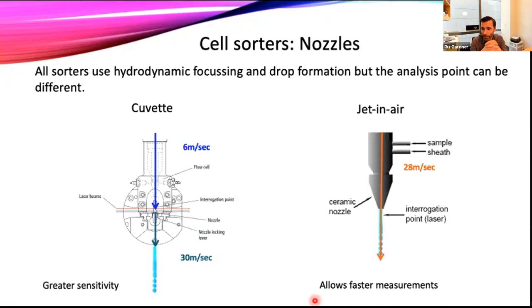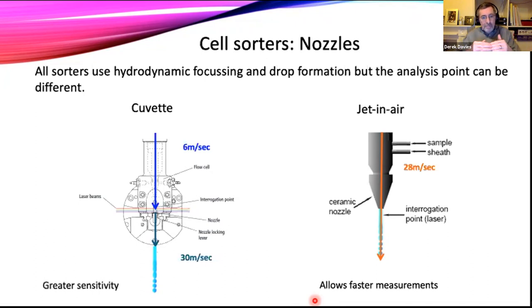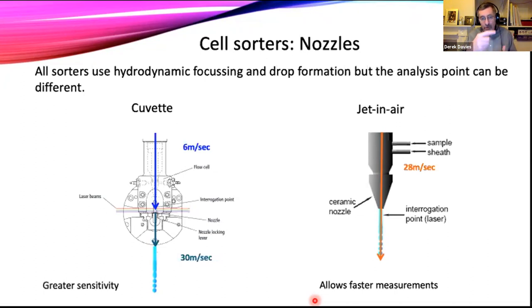Another question: do cells get randomly charged, or is there a mechanism based on cell surface properties? Your cells don't get charged at all — it's the drop that gets charged, on the outside of the drop. By the time your cells end up in a collection receptacle it will have naturally discharged, so it shouldn't affect your cells. Another important question: how do you know the cells are separated from each other so they don't go through the laser at the same time? Sometimes we have more than one cell in the laser beam at once. Sometimes we can separate those signals and remove them as doublets. If two cells come very close together on a cell sorter, sometimes we can't make a measurement of the second event, and that can impact purity — so in many sorters we would abort that measurement, called a hardware abort, because we don't know what the following cell is.